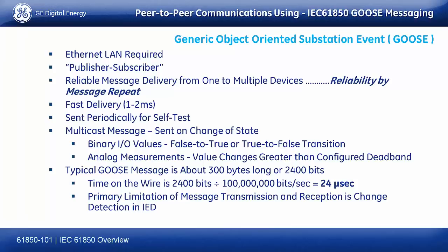Okay. Now, one of the things is we never know. So one of the challenges, if we look at GOOSE messages, is because I'm just publishing it multicast and there's no acknowledgement that it's been received, and it only gets published when there's a change of state in any one of the data values of data set items, that GOOSE messages may not be published, right? And your subscribing device doesn't hear from you in a while, starts to wonder what goes on, right? The subscribing device may actually disable this GOOSE message, saying there's something wrong with the device. So what happens is a heartbeat message is sent every once in a while just to say, hey, I'm still here and my data hasn't changed. I'm here, present, right?